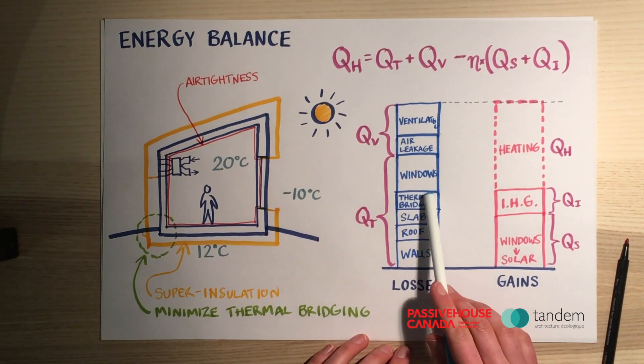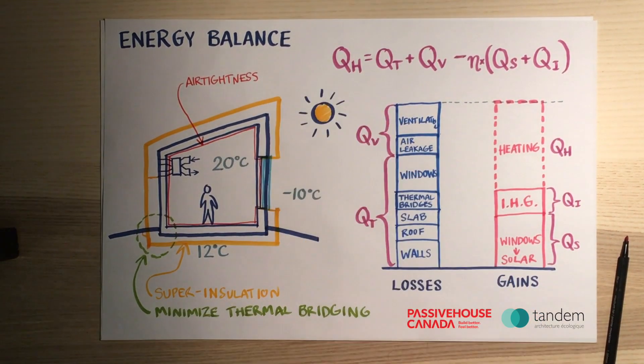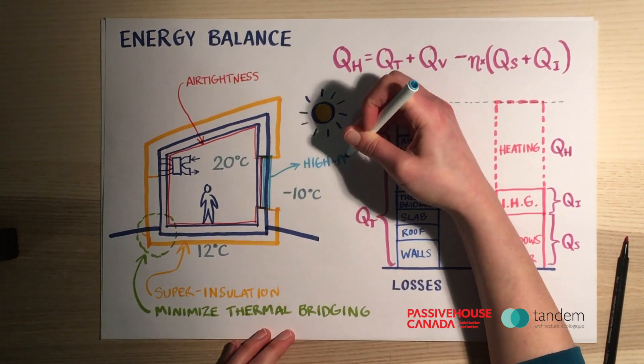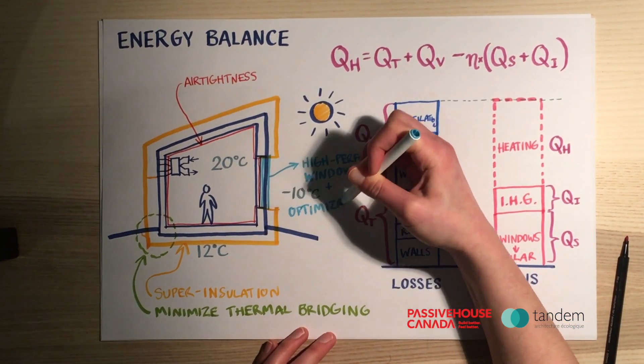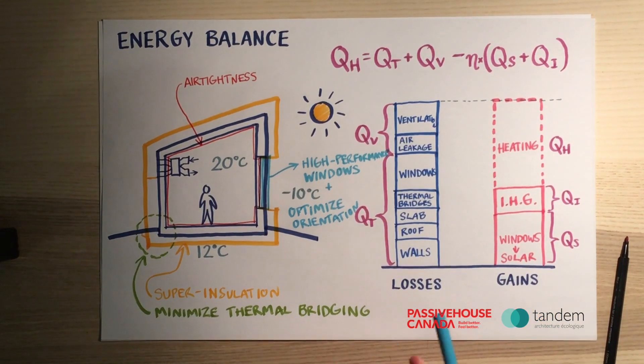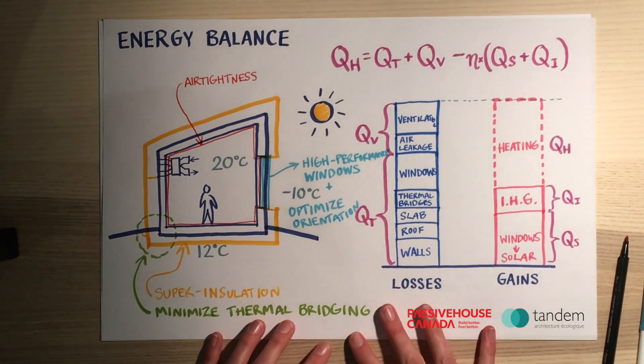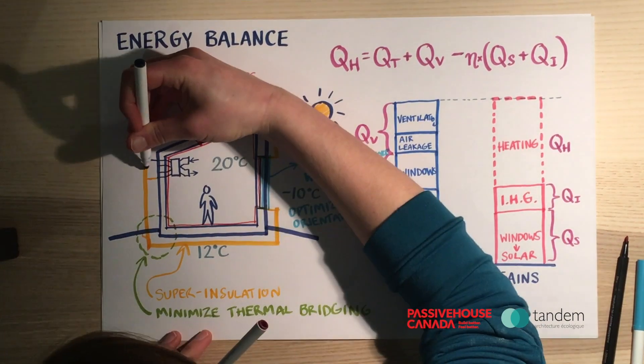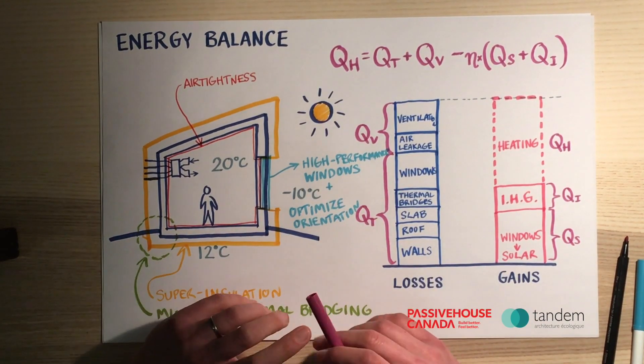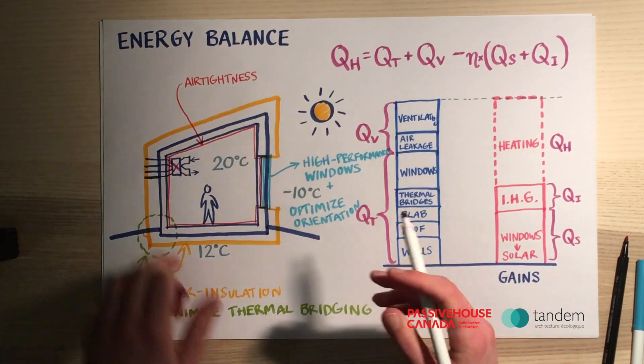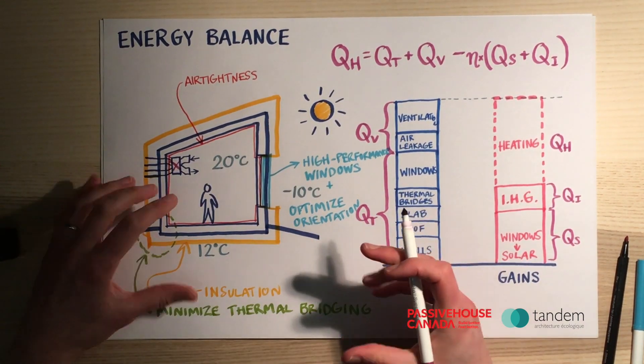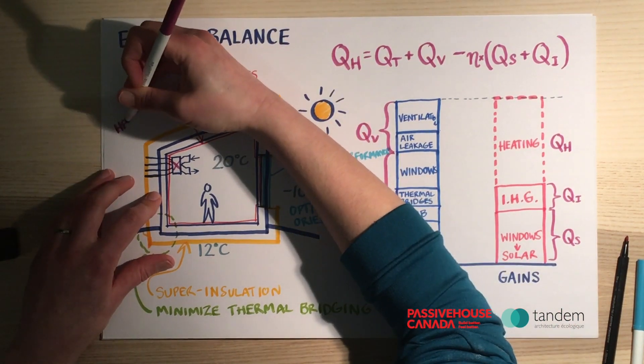We will pick high-performance windows and optimize their solar orientation — triple glazed, with a good insulated frame and a good installation detail. And lastly, when it comes to our ventilation system, we're going to pick a system that includes heat recovery, so that the warm air being evacuated from the building preheats the fresh air coming in. We're not cross-contaminating, but we are exchanging heat to reduce the ventilation losses.